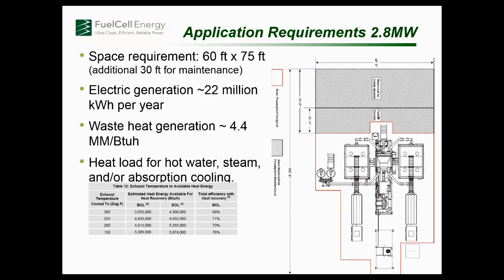That table below gives you an idea of how efficient the unit is, depending on what you're doing with the waste heat. We replace the fuel cell stacks about once every 5 to 7 years, and when we install a fuel cell, it's going to decrease in electrical efficiency and increase in waste heat efficiency over the course of that stack's lifetime. That's why you see the difference in the two middle columns between the beginning of life and the end of life.